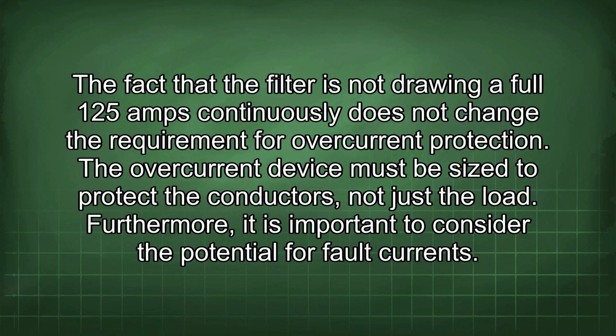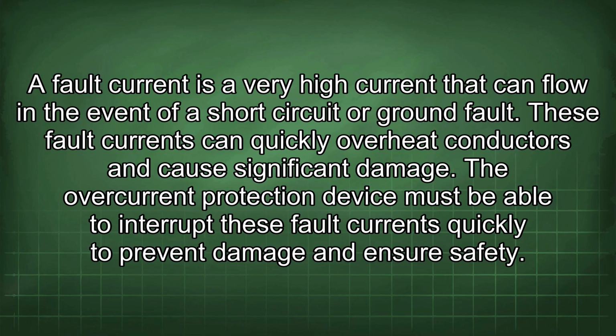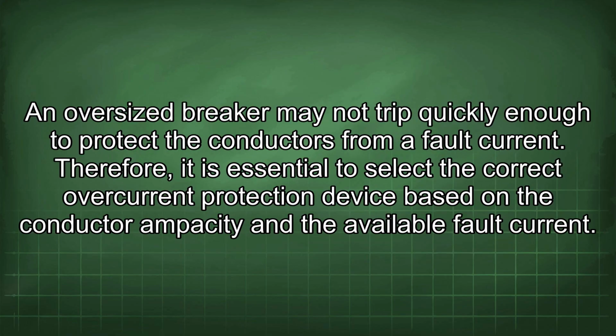Furthermore, it is important to consider the potential for fault currents. A fault current is a very high current that can flow in the event of a short circuit or ground fault. These fault currents can quickly overheat conductors and cause significant damage. The overcurrent protection device must be able to interrupt these fault currents quickly to prevent damage and ensure safety. An oversized breaker may not trip quickly enough to protect the conductors from a fault current.